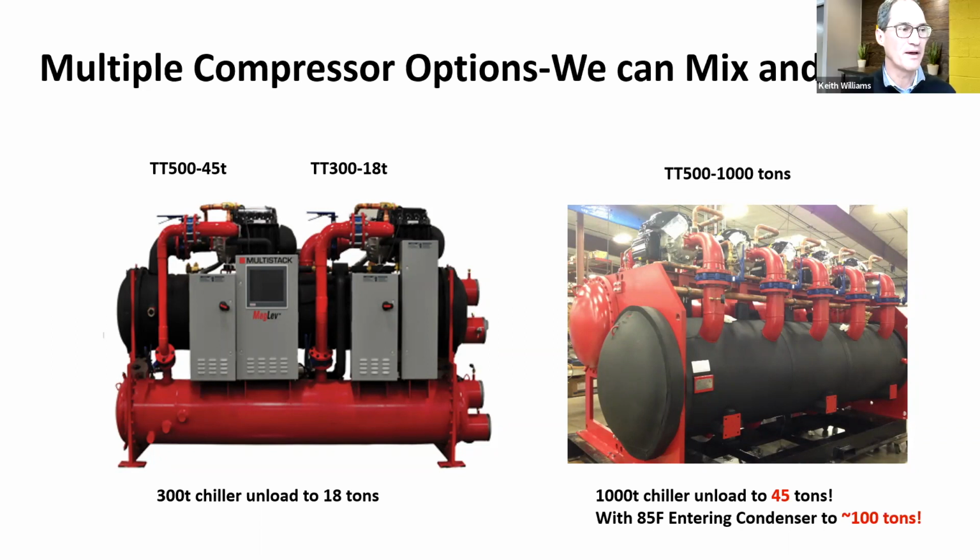Oh, great. I've got another question here. It's from Melina. Have you seen an application or request from an owner where they want to run the condenser and chilled water through the chiller while the compressor is off until the condenser water is warmed up? Usually when the system transitions from water economizer to mechanical cooling. Just like to hear your opinion on that.